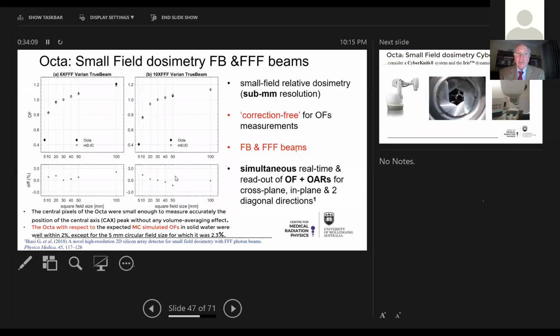I just would like to show you an application of this detector for output factor verification for small fields. We developed these detectors in such special packaging, which does not require any correction. Most detectors in small field dosimetry, as you remember, the diamond detector, the stereotactic radiation therapy detector, PTW, and some nuclear ones, require some correction. This detector immediately measures the profile and measures the output factor with the central pixel and does not require correction. It is also applicable in FFF fields. So we're quite happy with this development.